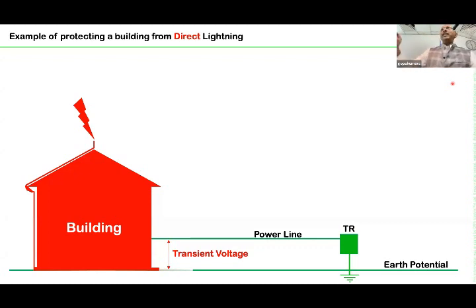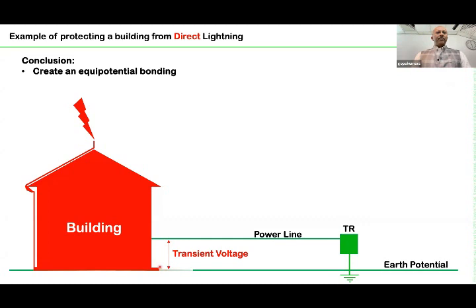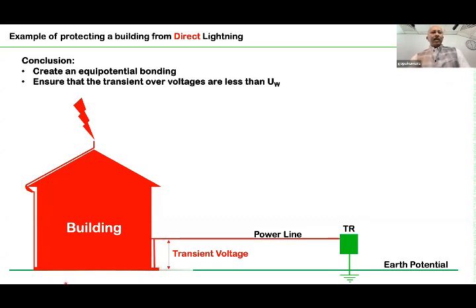Now what should we do? Between the lines and the earth, you will experience the transient overvoltage, which is nothing but the potential difference. Now I have made this place where I am moving the cursor. I will go back. You see, I have made a red color line. The idea of this red line is that with an SPD, I have made an equipotential bonding at the service entrance, meaning at the meter board. As a result, the entire building as well as the incoming services are at the same potential. So there is no failure.